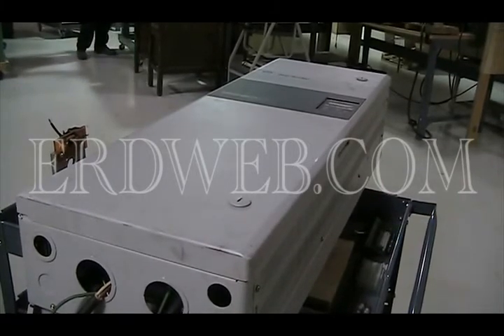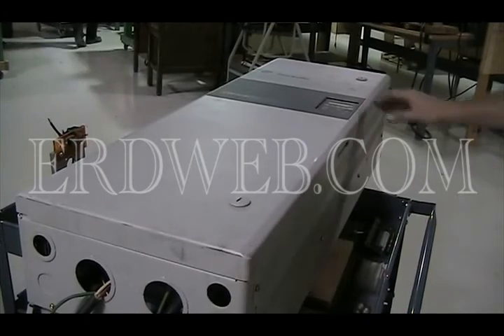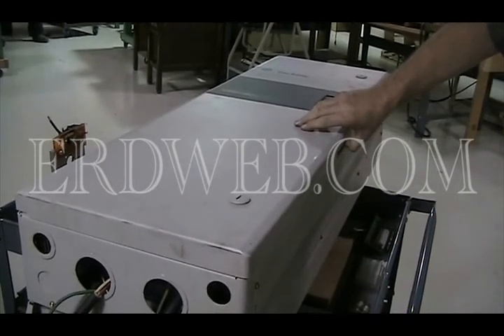Normally this drive will be tested on about a 20 horsepower motor. But other than that, it's a fine drive. And in this particular case, it had a bad control board.